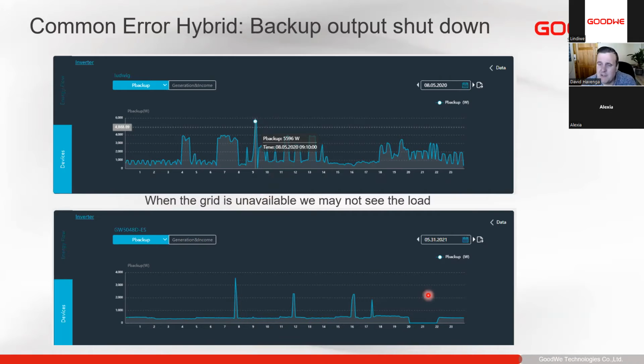But when you only have batteries and we're limited to battery discharge current, we cannot over discharge the batteries. So for battery safety, so the batteries don't shut off or anything like that, we normally switch off quicker. Because of that quick shutdown, you don't always see the overloads. But on the back end, we can have a look and get a message that says what the overload is. So this customer had fewer batteries. We do see higher spikes, but on the back end, we can see that it did report an overload error.